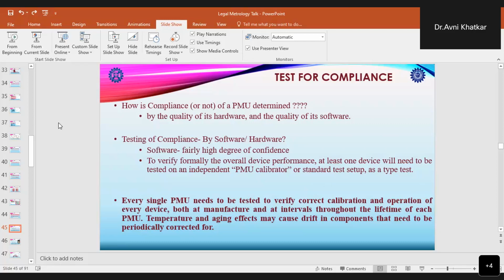Also, every single PMU needs to be tested in order to verify correct calibration and operation of each single device, both at the manufacturer end at the time of manufacturing and at specific intervals throughout the lifetime of each PMU, because temperature and aging can also affect and cause drift in components that need to be periodically corrected for.